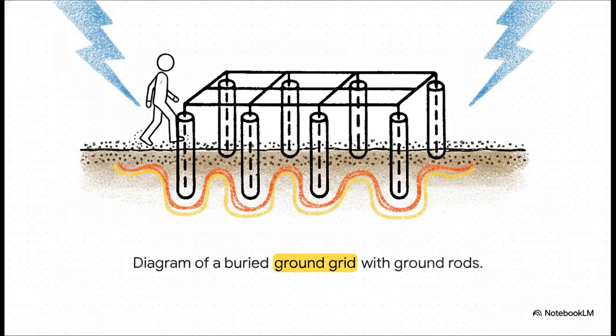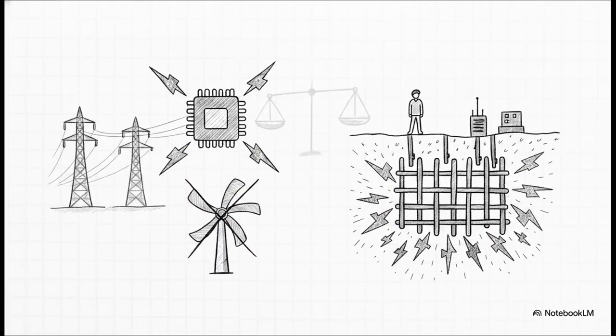And that mathematical solution becomes a physical reality, a massive, buried matrix of interconnected copper cables and deep ground rods. This entire grid is buried right under the crushed rock of the substation. When a massive fault current enters, this grid safely captures it and evenly disperses that deadly voltage deep, deep into the earth. It lowers the resistance and ensures that the surface voltage remains completely flattened, which keeps anyone walking above ground entirely safe.